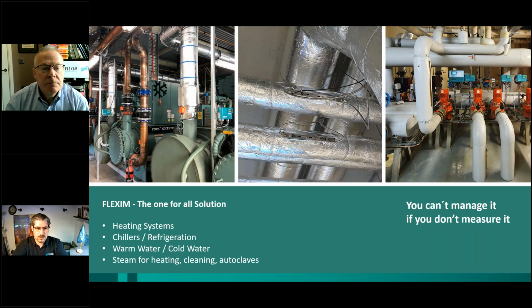Again, this is a one-for-all solution where you do not need to worry about which kind of meter you now need for this special application. Everything can be done with this non-invasive clamp-on meter, and it's very easy to design or lay out for you, because the main thing you need to consider is pipe diameter and the proper transducer. So if you have an inquiry for a flow measurement, you can ask Flexim, I have a need of a thermal energy measurement on a DN 150 millimeter pipe. So this is the according transducer you need, and that's it. You do not need to worry about flow ranges or any other things. It's quite easy to lay out and to install, of course.